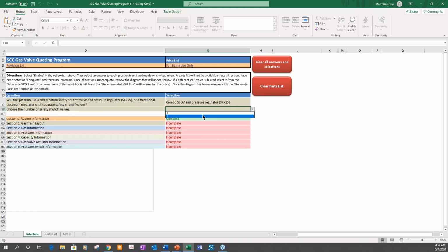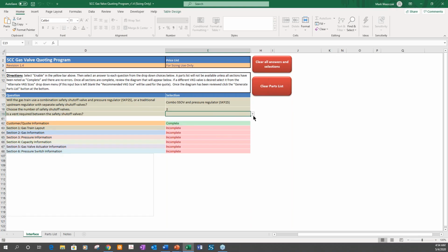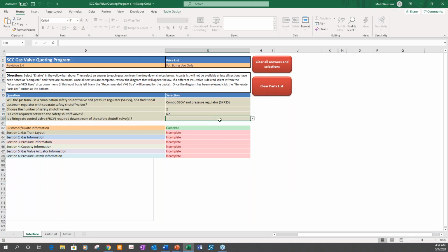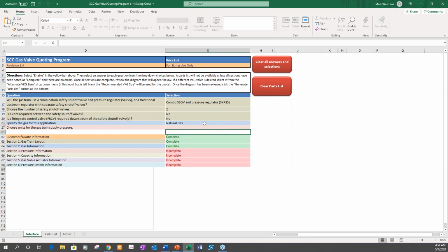Choose the number of shutoff valves. We'll select 2. Is there a vent required? We're going to say no. Do we require a firing rate control valve? We're going to say no. It's already selected the gas for you. If you are looking at a different type of gas, you could just go to the drop-down menu and select it. But for this purpose, we're going to use natural gas.